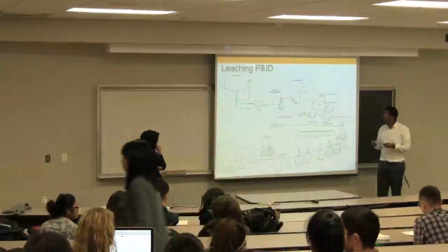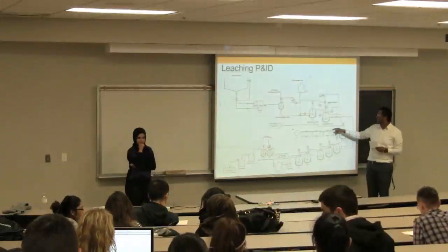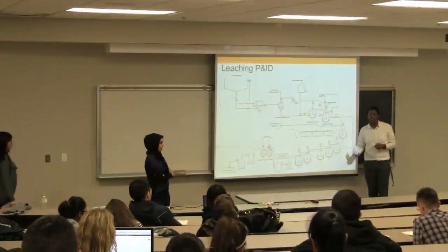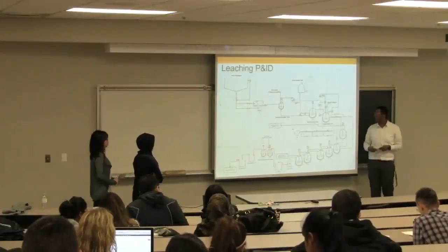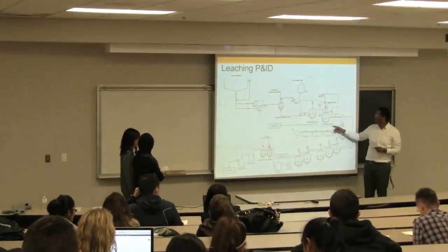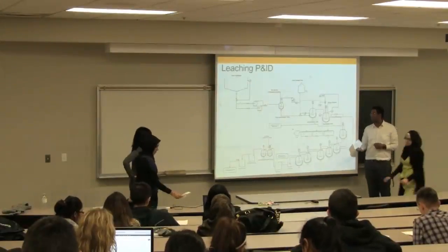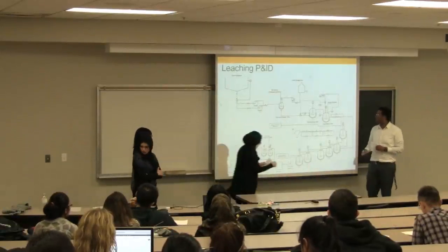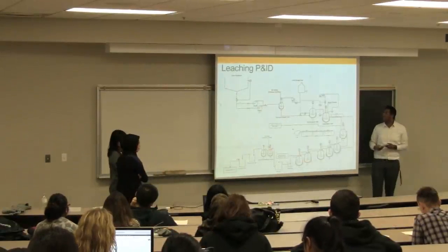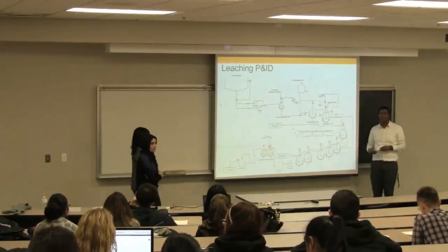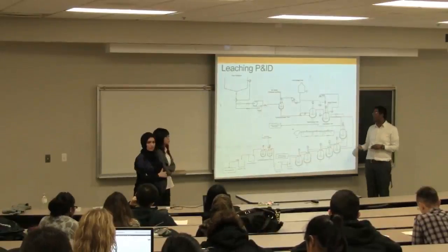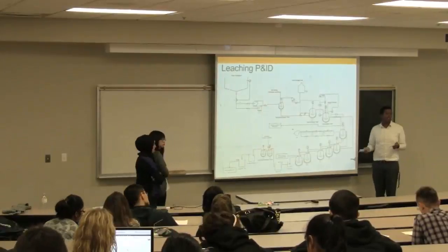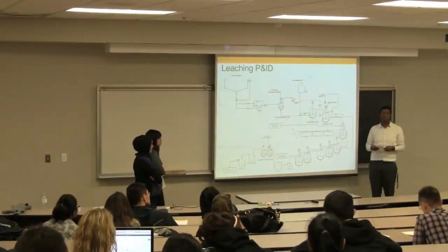What we have is the pH in the cyanidation tank is quickly dropping. Once the pH drops below 10.2, hydrogen cyanide gas starts to form, and we also lose valuable gold. Therefore we have a 15-minute window before the SIS system kicks in and shuts down the plant. Now we don't want that to happen. We want to continue production so we don't lose gold. So, if you guys have any ideas of what might be the problem.